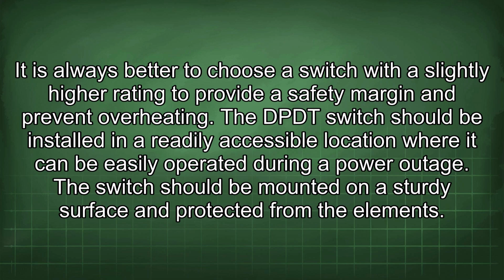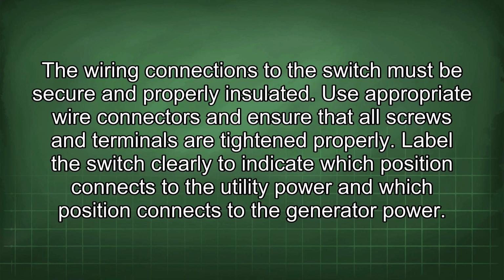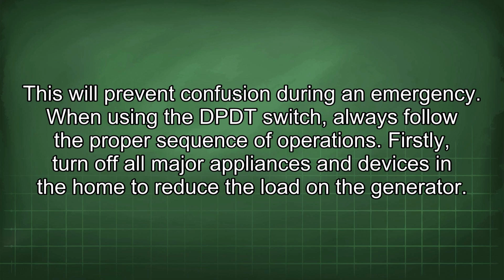The DP-DT switch should be installed in a readily accessible location where it can be easily operated during a power outage. The switch should be mounted on a sturdy surface and protected from the elements. The wiring connections to the switch must be secure and properly insulated. Use appropriate wire connectors and ensure that all screws and terminals are tightened properly. Label the switch clearly to indicate which position connects to the utility power and which position connects to the generator power. This will prevent confusion during an emergency.